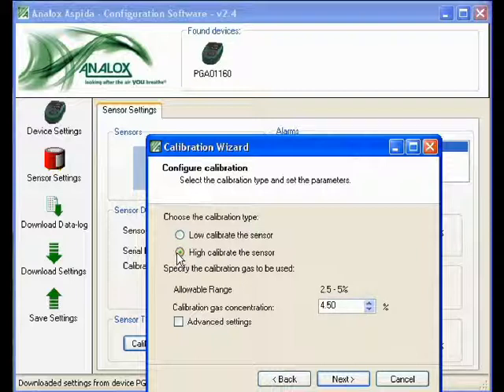We can change the gas settings to match those of the gases being used to calibrate the system. In this case, we're changing the high setting to 5.0%.